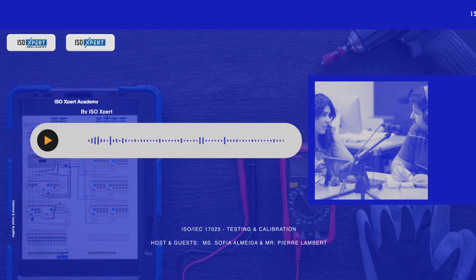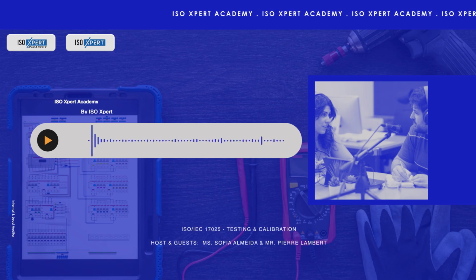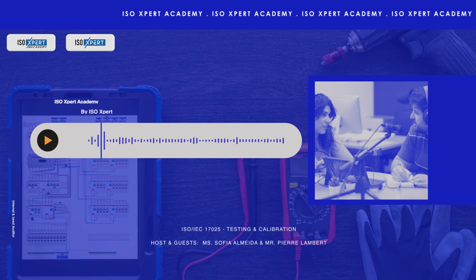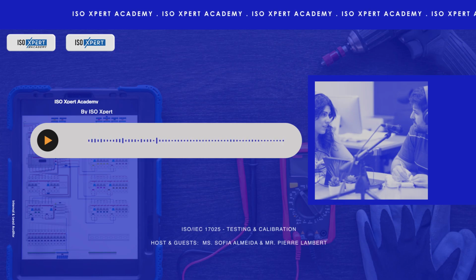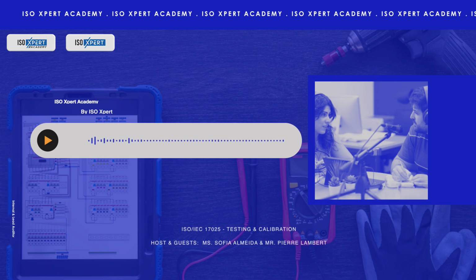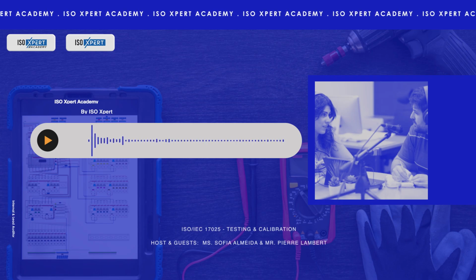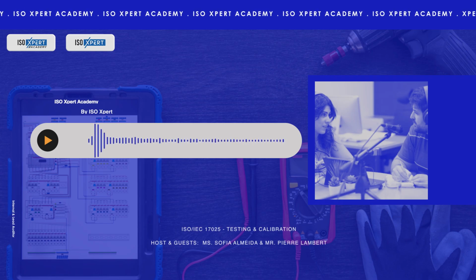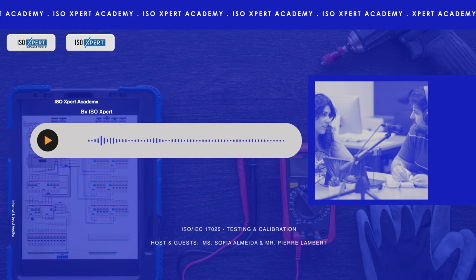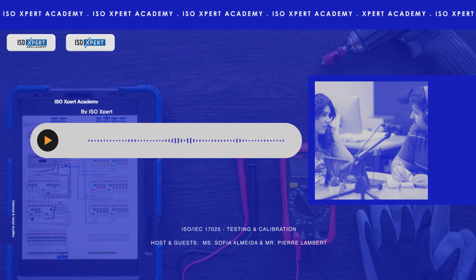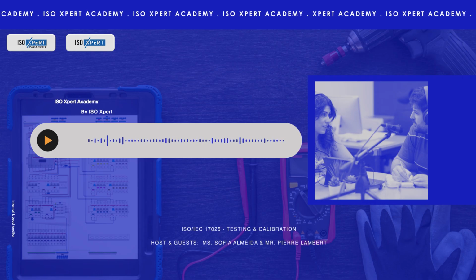Next up, 6.3 facilities and environmental conditions. This one seems pretty straightforward, controlling the physical environment so it doesn't mess up the results. Right, but the devil's in the details. Auditors inspect logs for things like temperature, humidity, sometimes even vibration levels, all things that can subtly or not so subtly affect sensitive measurements. They also look at lighting, ventilation, general cleanliness, separation of incompatible activities. Imagine trying to measure trace contaminants in a dusty room or run sensitive electronics next to a big centrifuge. Yeah, you can see how that would be a problem.